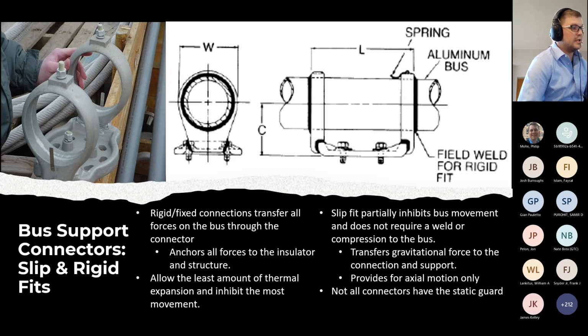Now, for a slip fit style, it inhibits movement, but it transfers the gravitational force to the connection point, but then it'll also provide that axial motion for the thermal expansion to move. Not all have this static guard right here, which is labeled as spring up here.